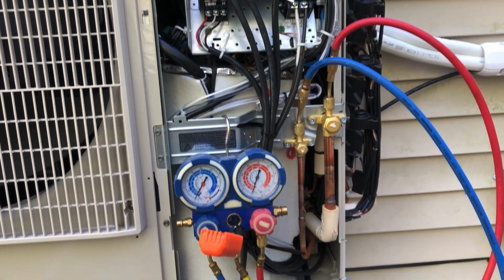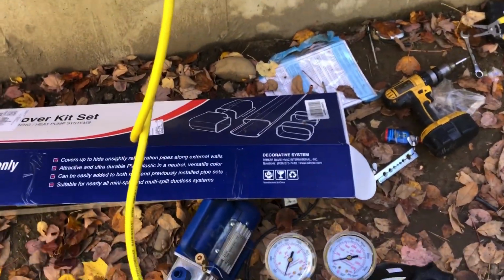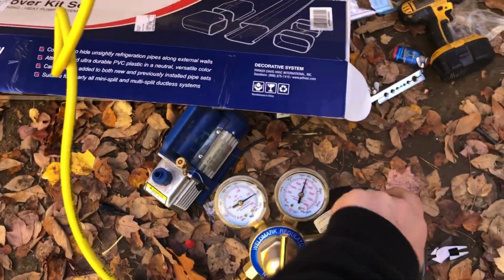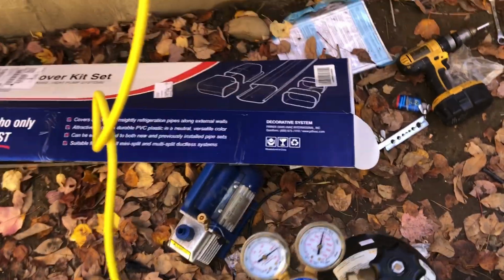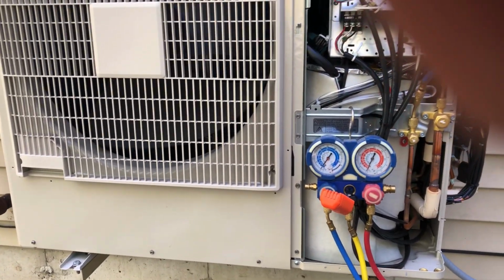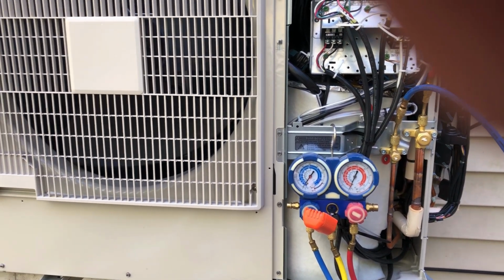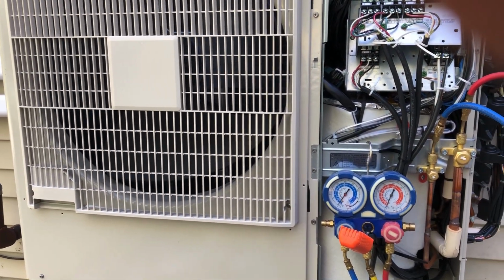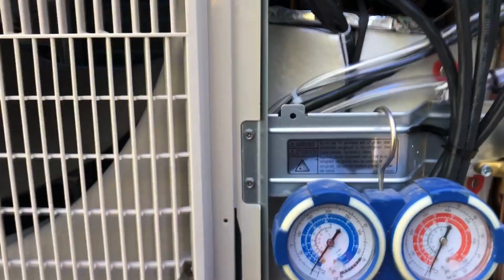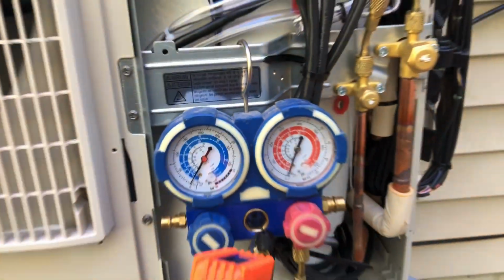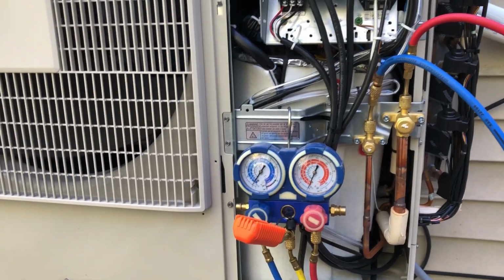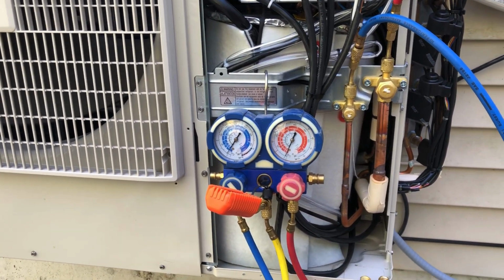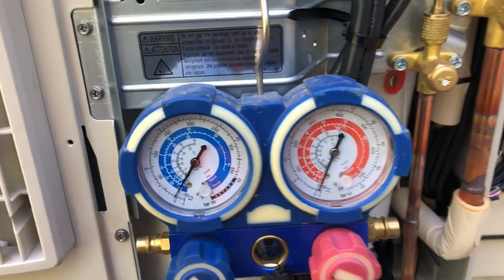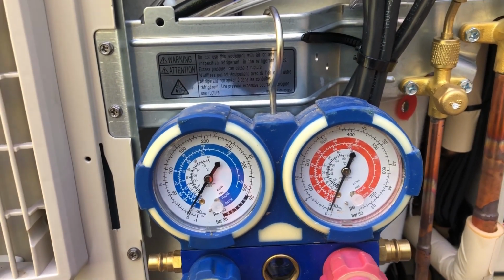I'm just going to pressurize the line sets. I'll open my regulator and pressurize to about 500 psi, between 400 and 500, and then look for any leaks in the fittings. I'll pressurize it, hold it, and leave it. A lot of people say leave it for 24 hours, but I say just leave it for a couple of hours.